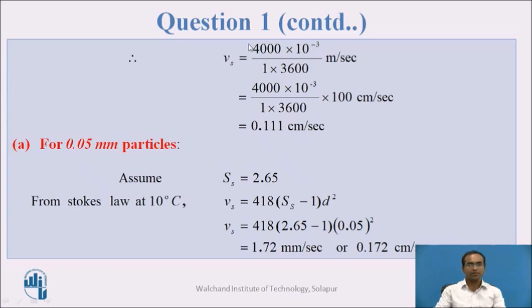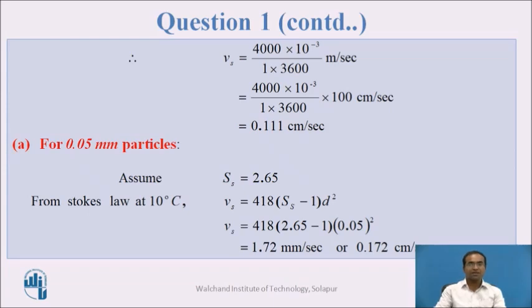By putting Q and A into the formula Vs equals Q by A, we get 4000 multiplied by 10 to the power minus 3, divided by 1 meter square multiplied by 3600 seconds. Converting to centimeter per second by multiplying by 100, we finally get Vs equal to 0.111 centimeter per second. This is the given Vs, calculated from the overflow rate.